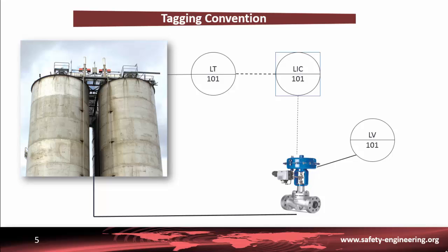Knowing the device tag number is required when filling out a work order or when discussing a field measurement with an operator or instrument technician. The tag number assigned to a field device is normally stamped on the tag attached to the device. All devices used together to perform a specific function are normally assigned the same loop number. For example, the flow transmitter and regulating valve used to measure and regulate the flow of a process stream may be assigned loop number 101.